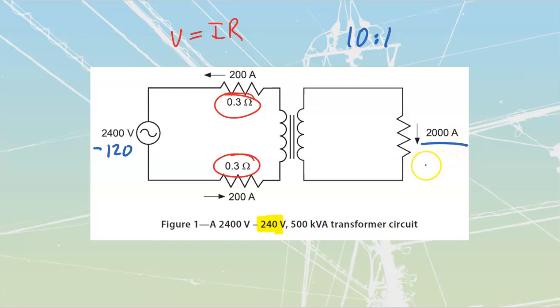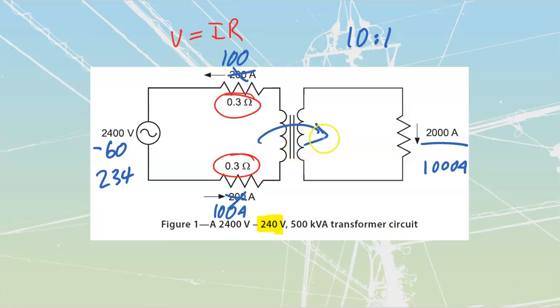But during the winter, this grocery store might only be running 1,000 amps, which would mean that, because it's a 10-to-1 transformer, these would be at 100 amps. And if we have 100 amps there, at 0.3 we'd be dropping 30 volts off of each of these, which means that we would be down to only a voltage drop of 60 volts off of here. So we would be at 2340, which would mean that by the time I carry that voltage back across here, it would be just 234 volts.